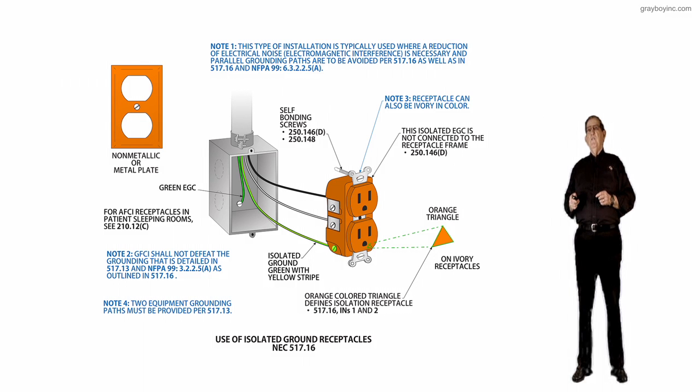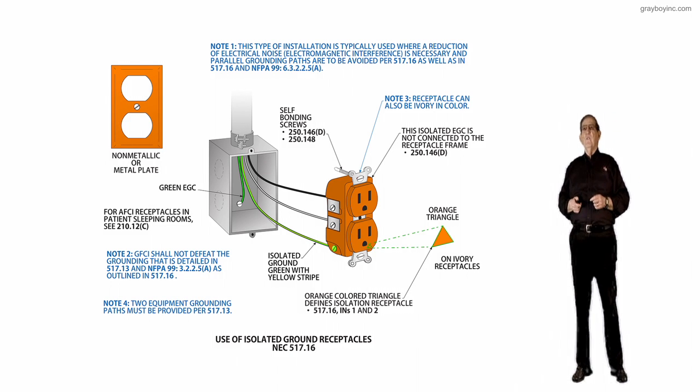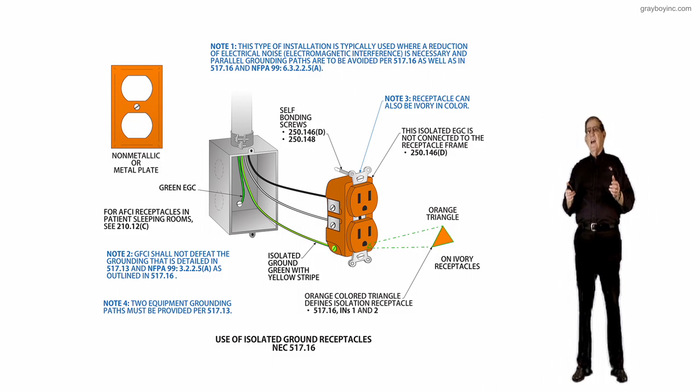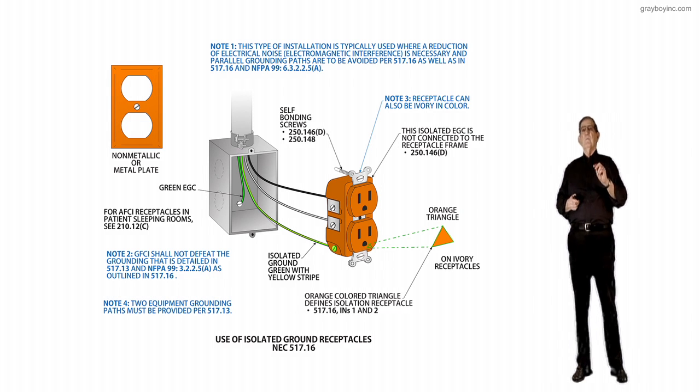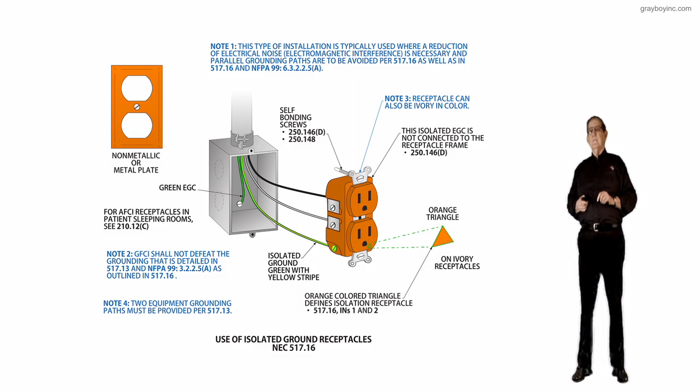If we review the isolation equipment grounding conductor, it's not connected to the receptacle frame. You see that pointing to the receptacle, the yoke, and so forth. This provides the isolation of the equipment connected to that receptacle, but it doesn't provide the redundant grounding required in Section 517.13 for receptacles installed in patient care areas.